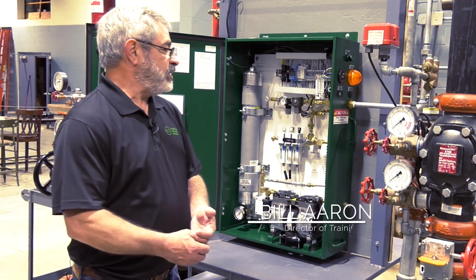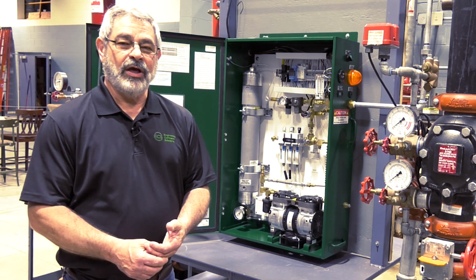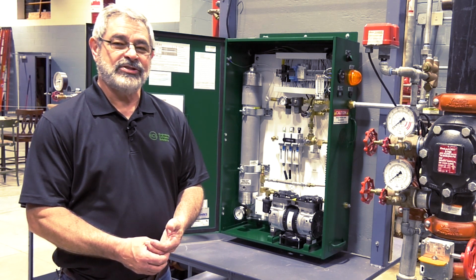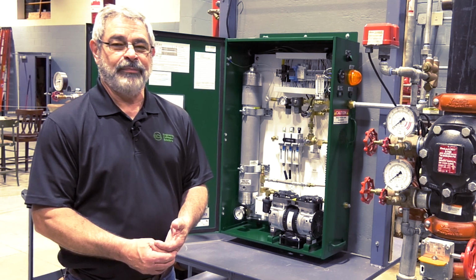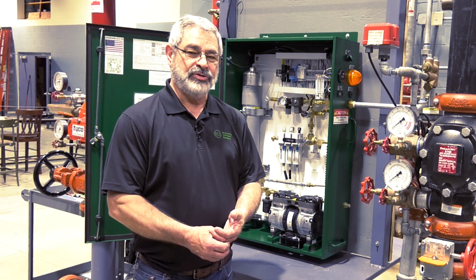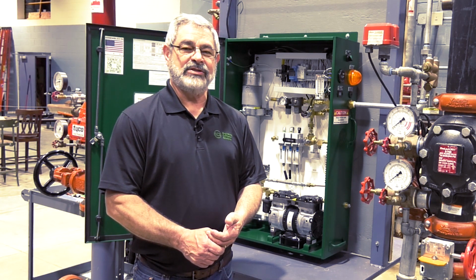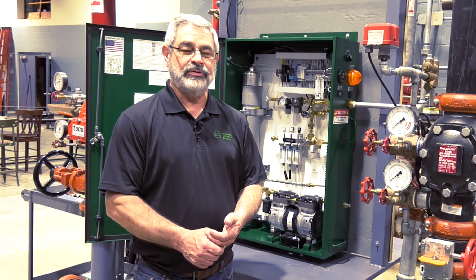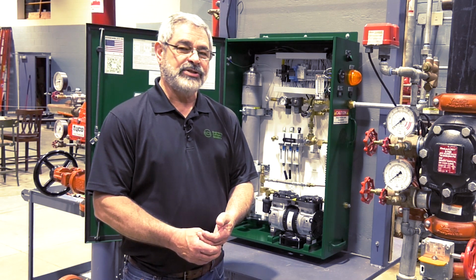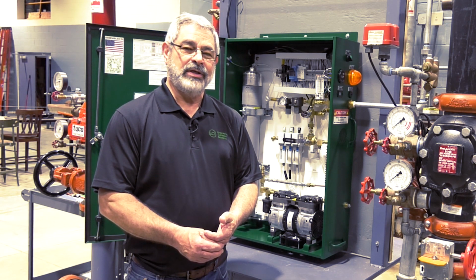We've completed the installation portion of the nitrogen generator. Now it's time to get ready to program it. There's some information that you need in order to program the nitrogen generator as far as the turn on and turn off pressures. Number one, we need to understand the supervisory gas operating pressure of the sprinkler system. In our application today, that pressure is operating at 30 PSI.